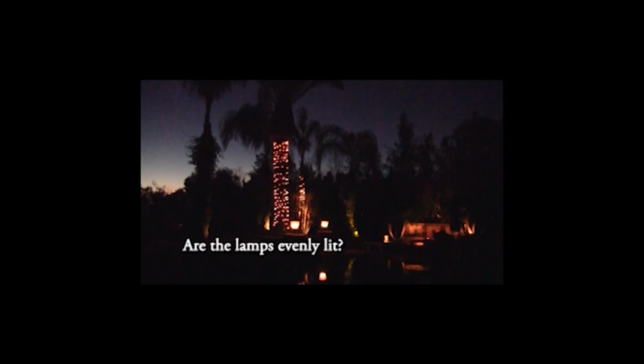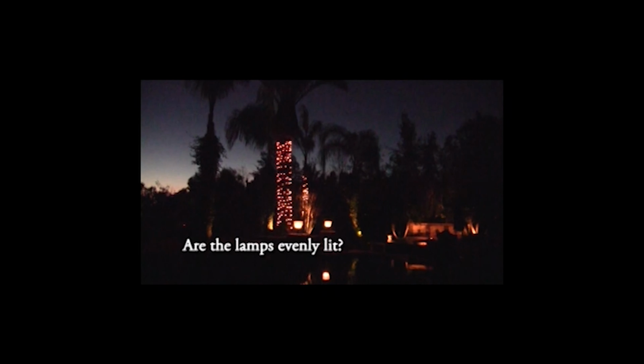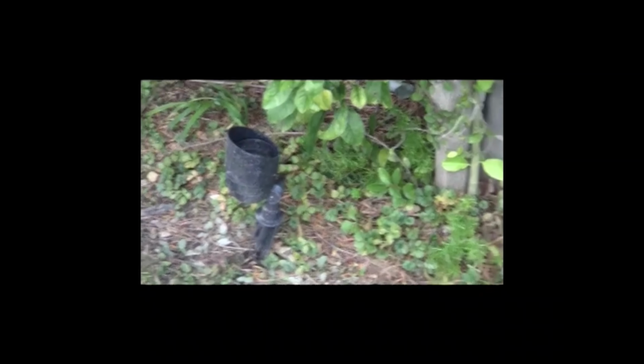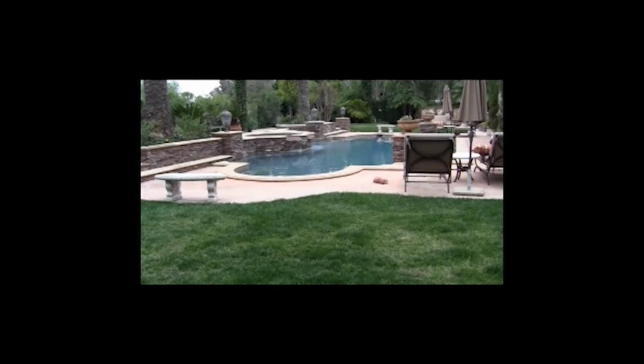Probably the most common complaint with large systems is that the lamps close to the transformer are really bright, while the lamps farthest away are really dim. The fixture over here should be just as bright as the one way over there. We're talking about just 12 volts here.